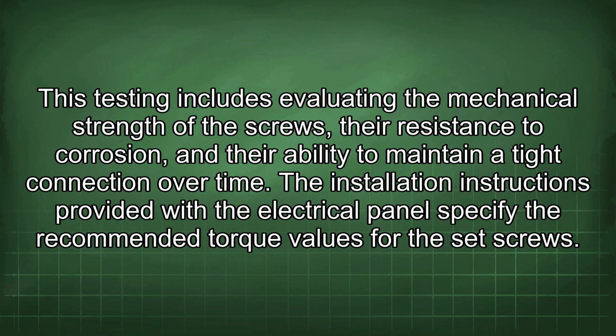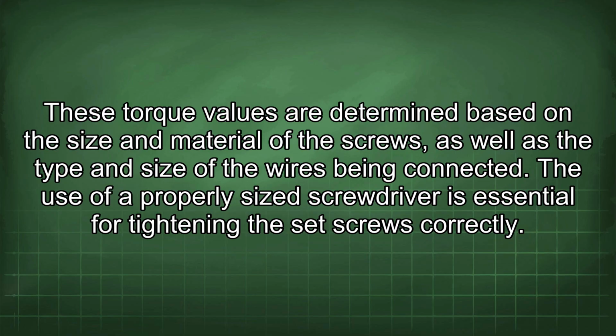The installation instructions provided with the electrical panel specify the recommended torque values for the set screws. These torque values are determined based on the size and material of the screws, as well as the type and size of the wires being connected. The use of a properly sized screwdriver is essential for tightening the set screws correctly.